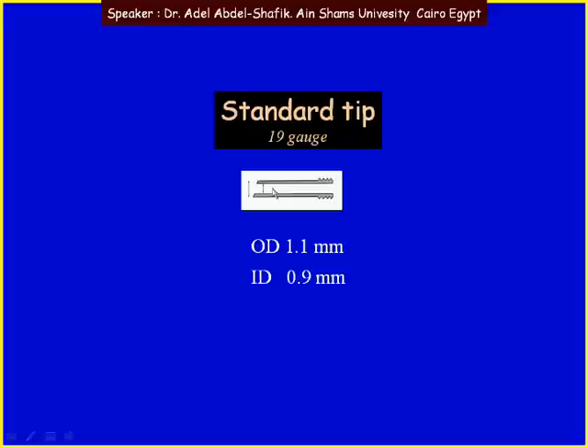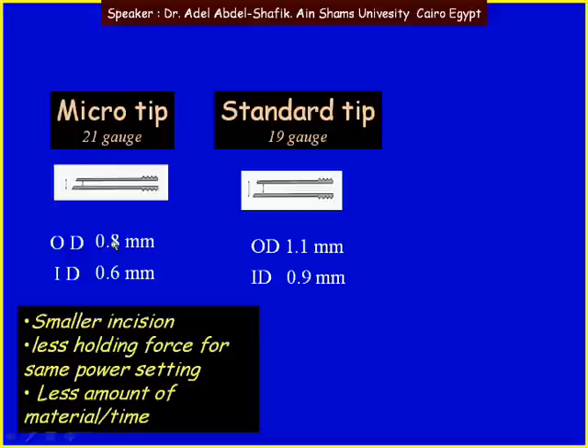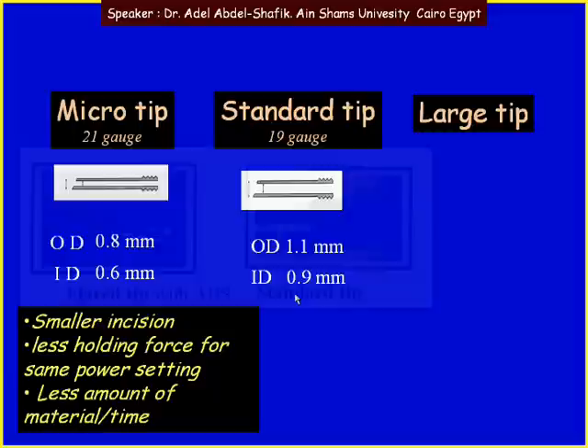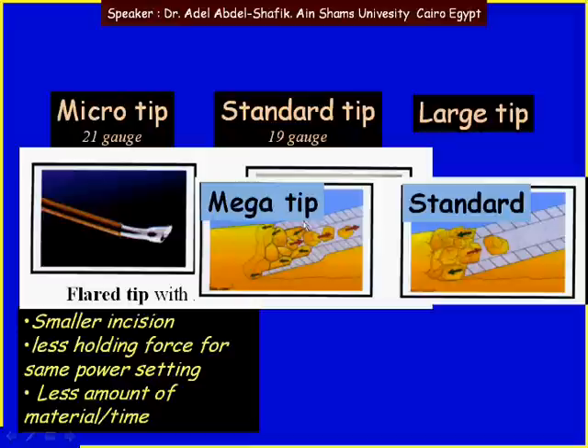The third strategy is to use a different phaco tip. The standard tip has an outer diameter of 1.1 mm and an inner cavity diameter of 0.9 mm. We can use a micro tip with an outer diameter of 0.8 mm and inner diameter of 0.6 mm. The micro tip can be applied through a small incision, but it has less holding force for the same power settings, and the amount of lens material removed over time is less. We can go for a larger tip size like the flare tip, which has a wide large opening at the tip of the needle.